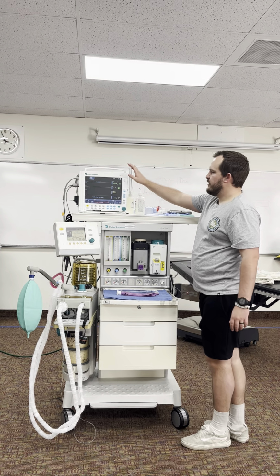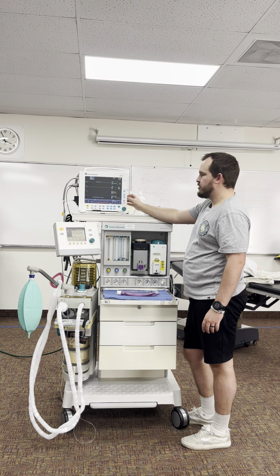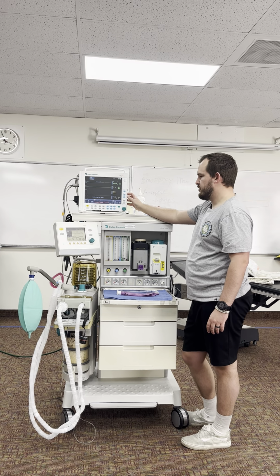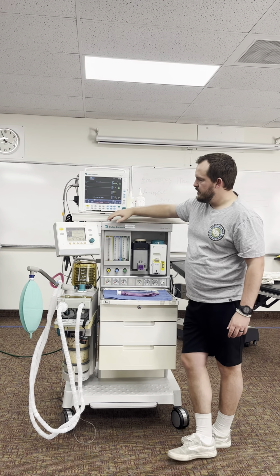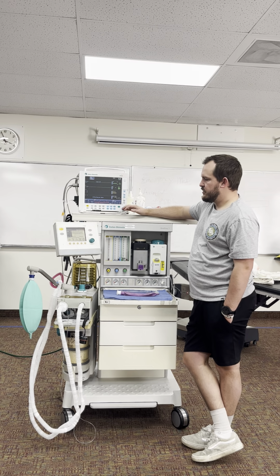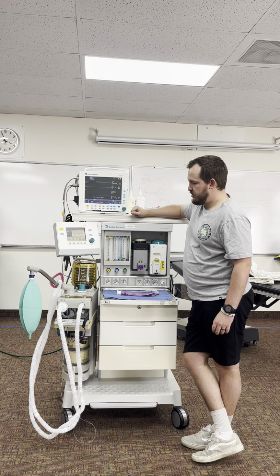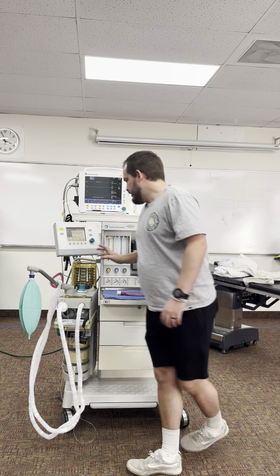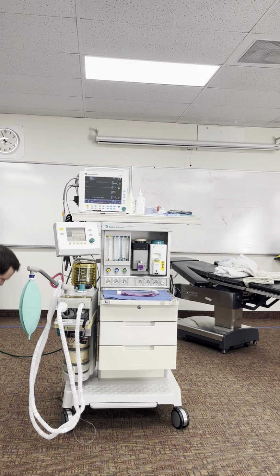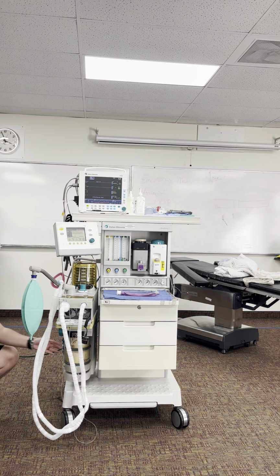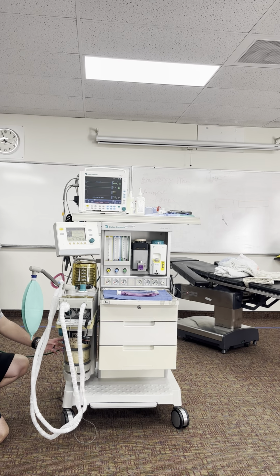While it's calibrating, I'm going to double check that my alarms are all set on my patient monitor and that they're good and in the right zone. And then I'm going to double check that my ventilator alarm is also good, specifically on the pressure limit, which it is. While it's still calibrating, I'm going to look at my CO2 cartridge over here. I'm going to make sure it's dry and not desiccated, and that the date isn't within the last couple days. It's appropriate and it's not used up.